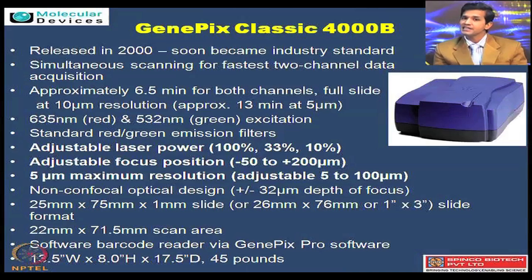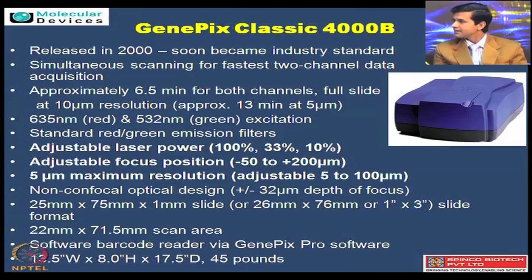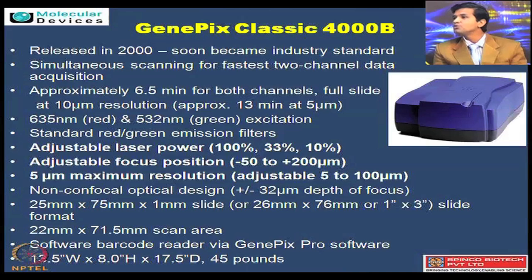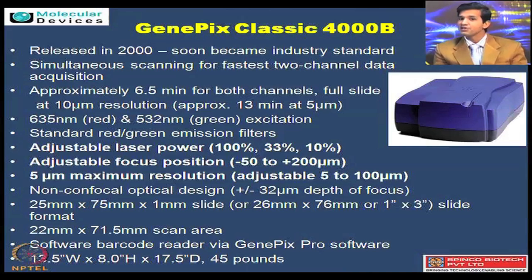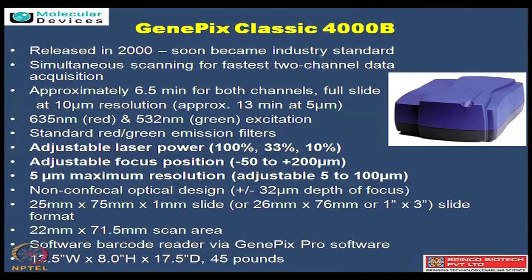The laser power can also be adjusted in the form of 100% to 33% to 10%, so based on what application and what intensity you want, the laser power can be adjusted as well. The adjusted focal position ranges from minus 50 to 200 microns, which allows you to focus in different ways giving different slide compatibility. It can go from 5 micron resolution up to 100 microns of resolution. Using the non-confocal optical design, any standard slide can be used for scanning, giving a wide range of applications.